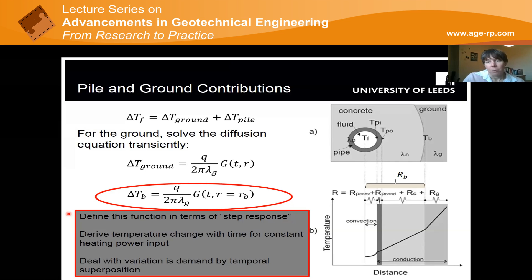Now, in reality, building energy systems don't operate in terms of constant demand. Heating demand is forever being turned on and off, increasing or decreasing, often on hourly or half daily time steps. However, the first thing we need to do is define this step response, and then we can use temporal superposition to deal with the fact that demand changes rapidly with time. I won't go into detail about that today because I want to focus on the fundamentals of thermal behavior, but it's a fairly standard approach that lets us deal with the fact that thermal demand varies all the time.